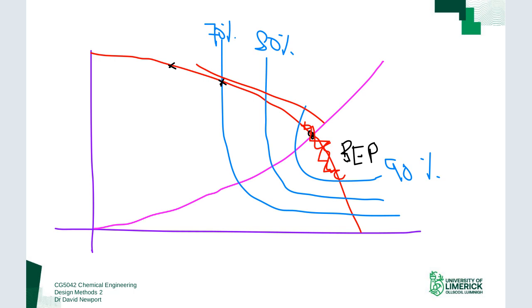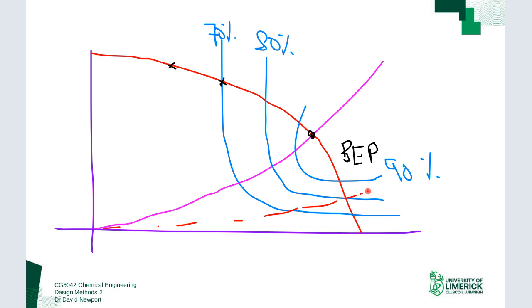So what we want in our design is always to try to get in that sweet spot of maximum efficiency to maximize pump life. How do we decide that? One option is we adjust our system curve — we increase the pipe diameter to produce a lower pressure system, or we may change fittings. If we're at a low-pressure operating point and want to shift higher, we may reduce the diameter or increase the pipe length to increase the pressure drop.